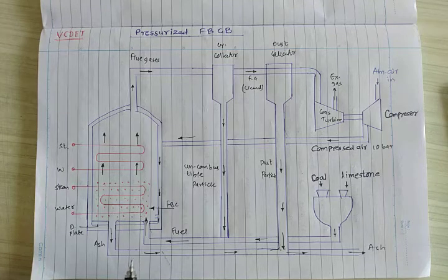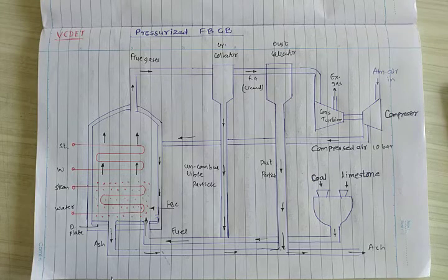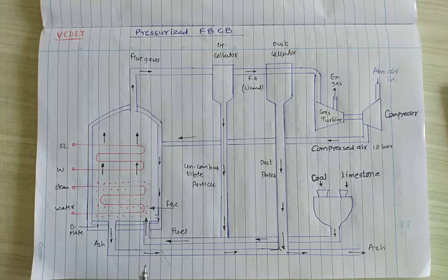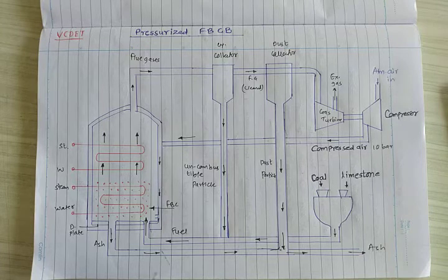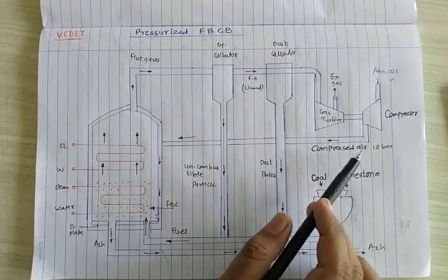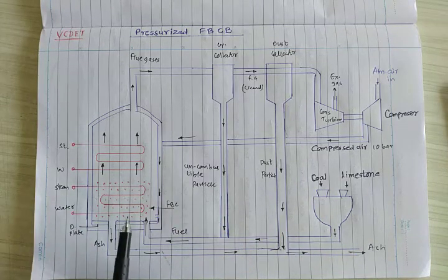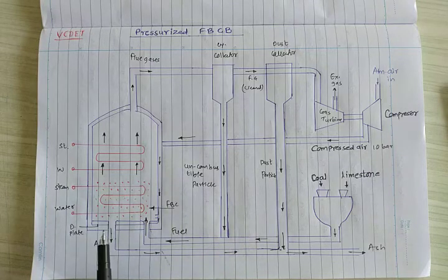The difference between the pressurized fluidized bed combustion and the circulating fluidized bed combustion is that in circulating FBC the operation is done at atmospheric pressure. Here in the PFBC, the air is supplied under pressure of 10 bar. For that purpose we use a compressor which compresses the air to 10 bar and then sends it towards the combustion chamber.